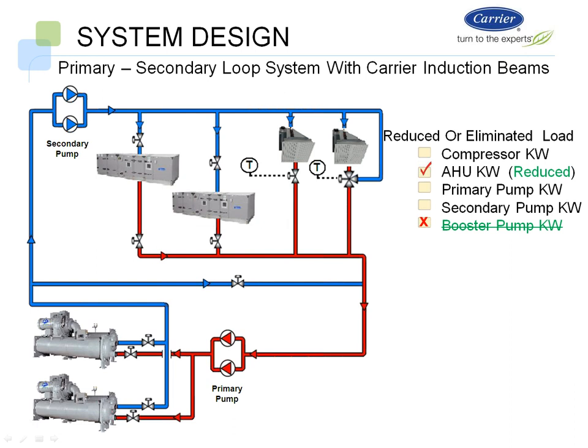And it takes out the complicated piping and control algorithms that have to be considered in the plant, now that you're just piping these right in and bringing cold water in and allowing them to do latent. Again, at that point, you would have to add some condensate capability, either gravity drain or a booster type, or gravity drain into a central pumping system.